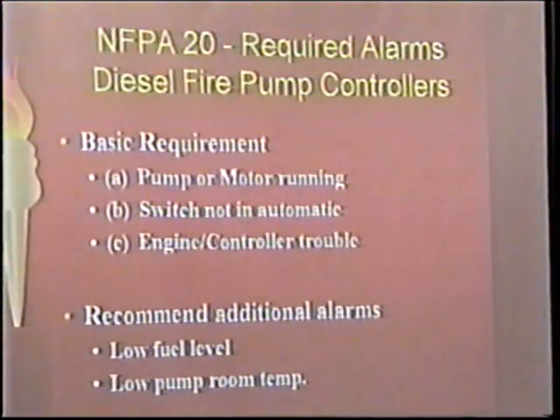Basic requirements here on diesels. Again, 3-point. Some people would say it's 4 because they want to break these 2 up. But the controller manufacturers are only required to put 3 points in the panel. So you'll find that most of them only have 3 points. The engine and the controller trouble is a common one. The switch not in automatic, meaning the selector switch, which is manual, off, auto in most cases. Some of the manufacturers still have a test position. Anytime that switch is anywhere but automatic, the fire alarm panel is supposed to know about it. And then the pump running.